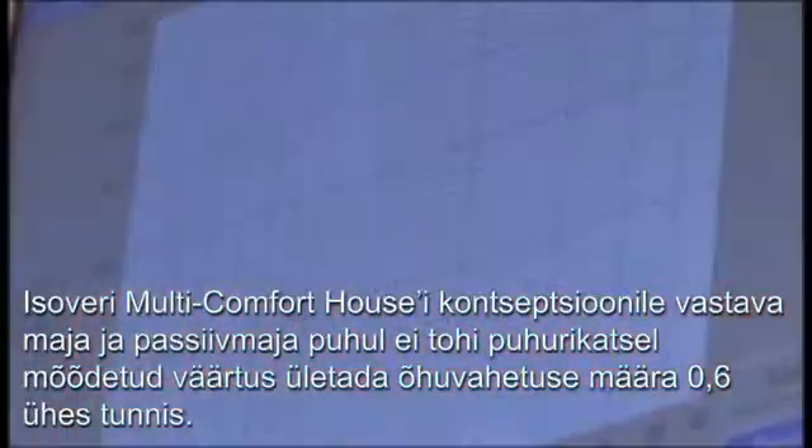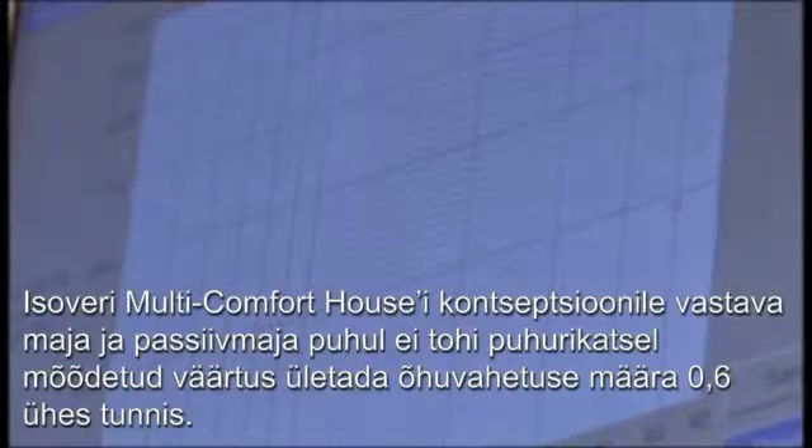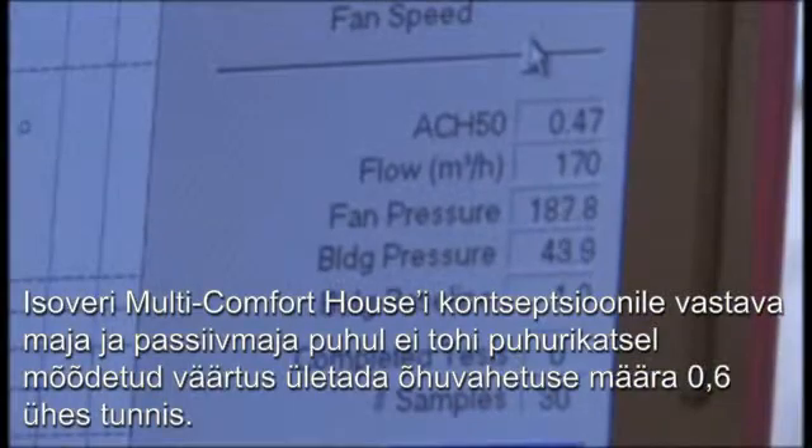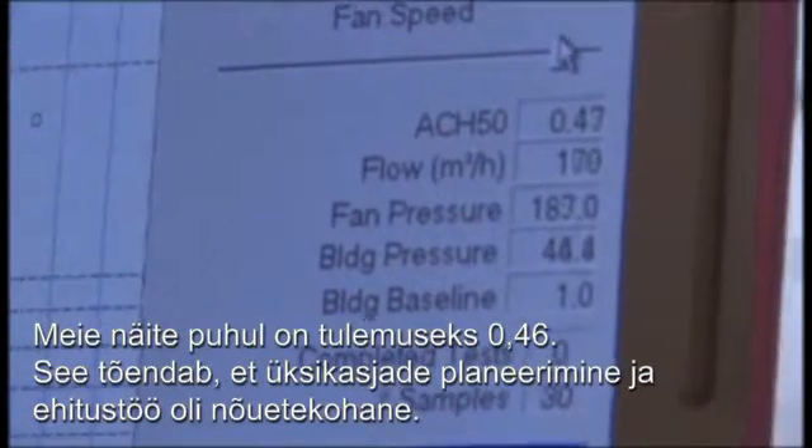For an Isover multi-comfort house or a passive house, the value measured by the blower door test should not exceed an air exchange rate of 0.6 per hour. In our case, the result is 0.46.